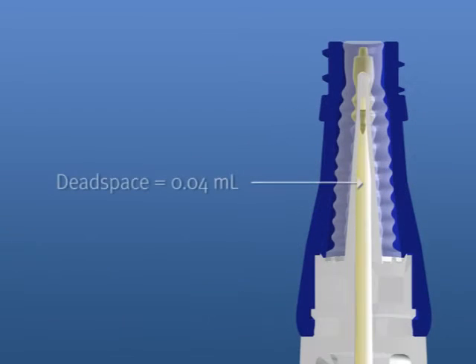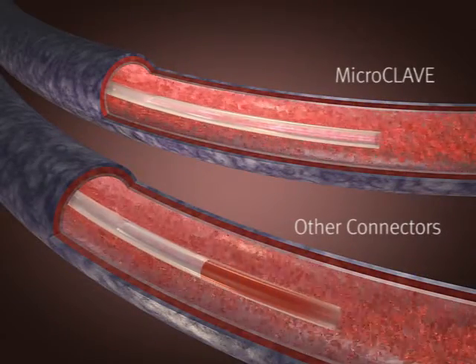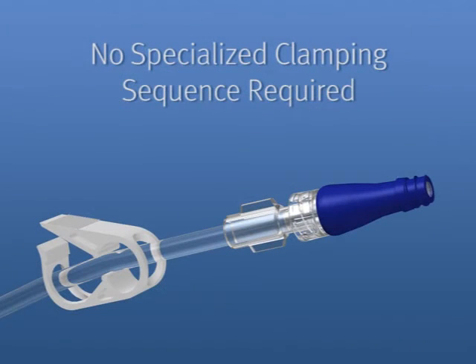The internal dead space of the Microclave is 0.04 milliliters, which helps to provide the neutral displacement feature. Neutral displacement means the backflow of blood into the catheter upon disconnect is minimized. This feature allows the clinician to use the Microclave without any clamping protocol, which eliminates the risk of error that can occur when using either negative or positive displacement connectors.